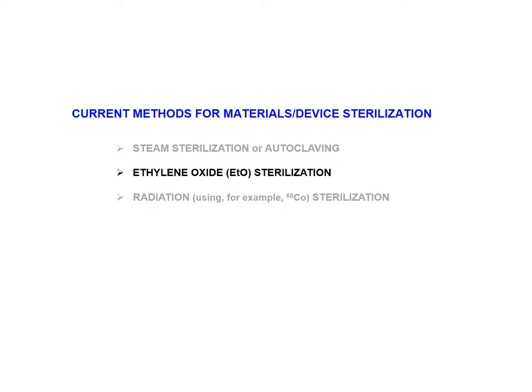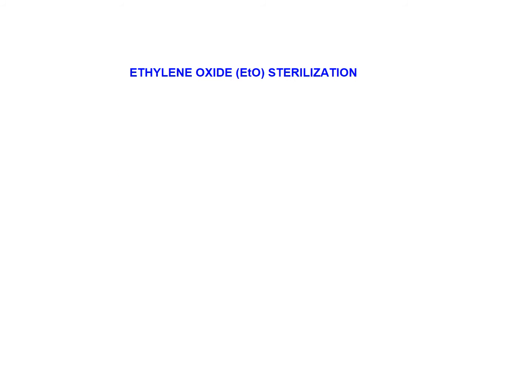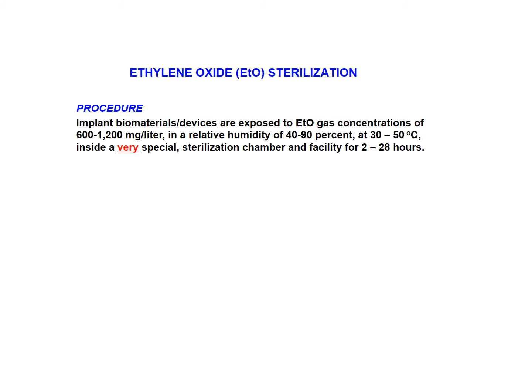One of the methods used is ethylene oxide sterilization. Ethylene oxide is usually abbreviated capital letter E, small case t, capital letter O, ETO. During the process of ethylene oxide sterilization, implant biomaterials and devices are exposed to ethylene oxide gas, concentration 600 to 1200 milligrams per liter, in a relative humidity of 40 to 90%, at a temperature of 30 to 50 degrees centigrade. Keep in mind, body temperature is 37 degrees centigrade. This process must take place inside a very special sterilization chamber and facility for 2 to 28 hours.